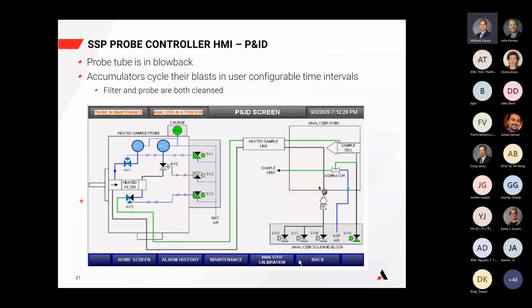Thanks. And you know what? I don't have a P&ID of that, and I probably should have. Rod's indicating that these different solenoids are controlling the zero and the cal and the validation streams here, but then it drives it up to here so that we come back through the sample pathway here. So we are going up to the probe, and we do go through the heated filter when those are occurring.